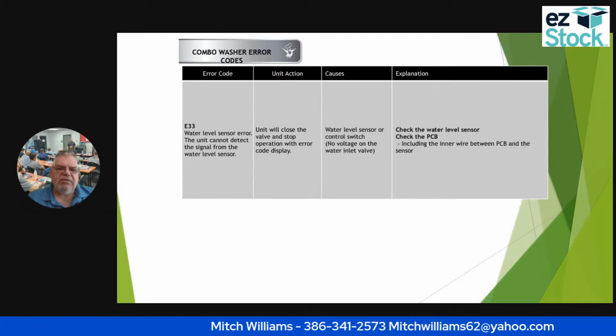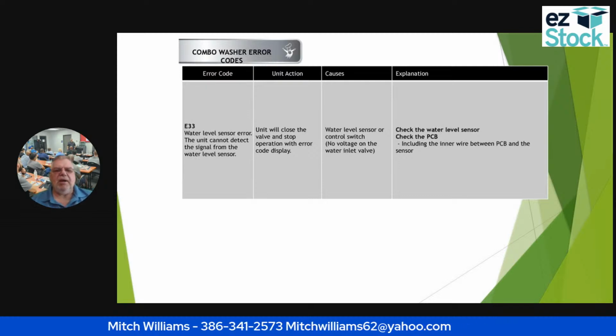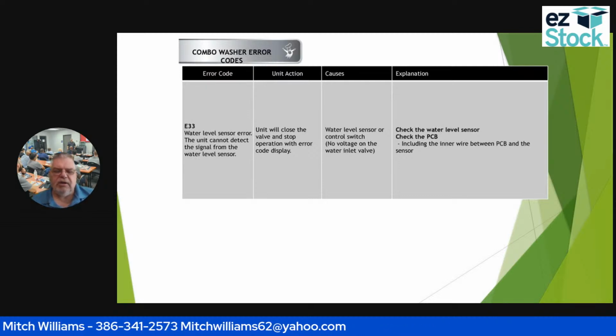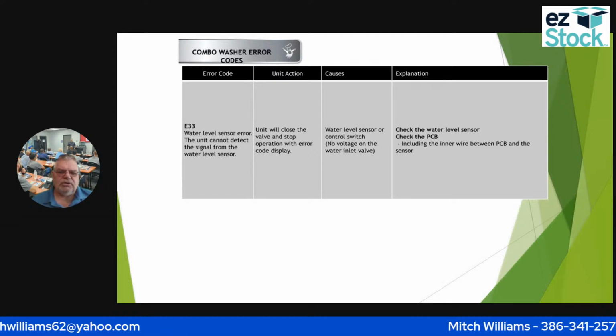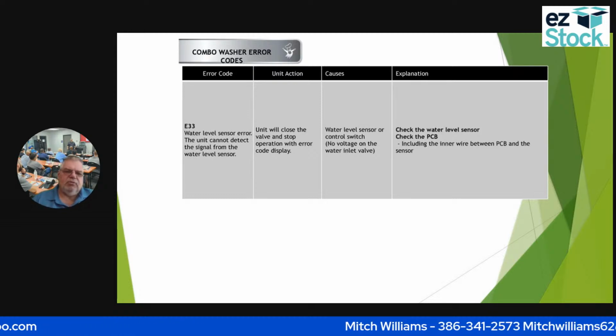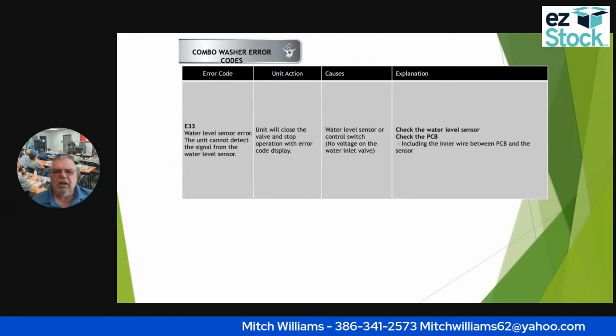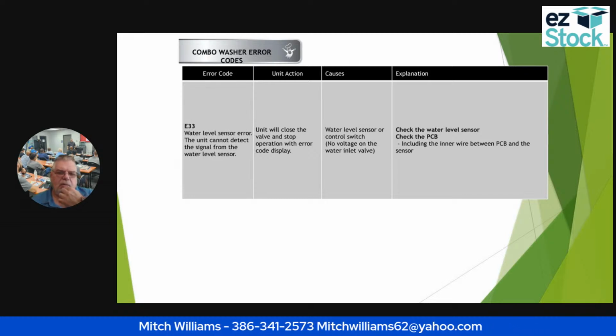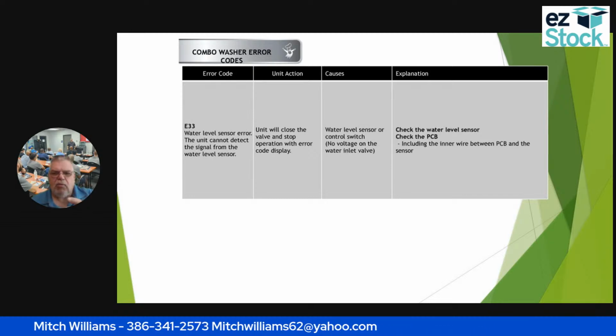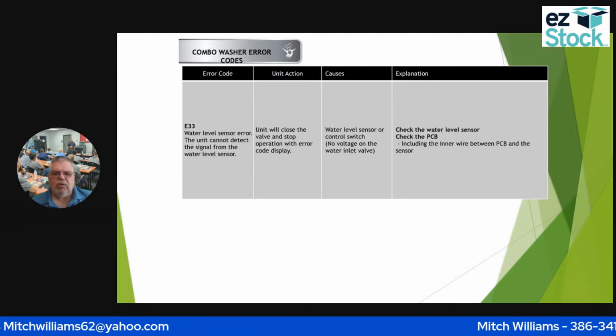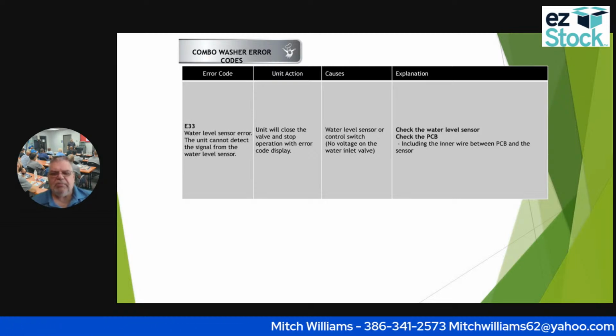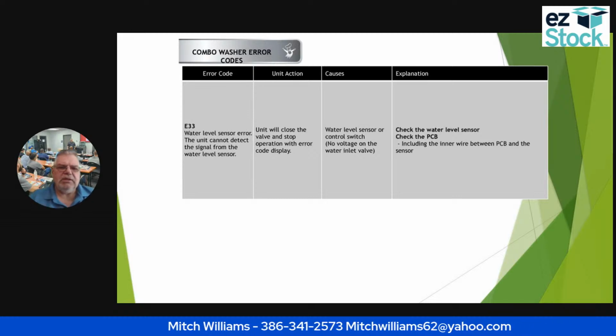So if I have an E33, that tells me that my water level sensor has an error. So the unit will close the valve and stop the operation with an error code. That usually tells me that my water level sensor, or my control switch is going bad. So what I'm going to do is check the water level sensor, then I'm going to check the PCB. It's pretty simple.